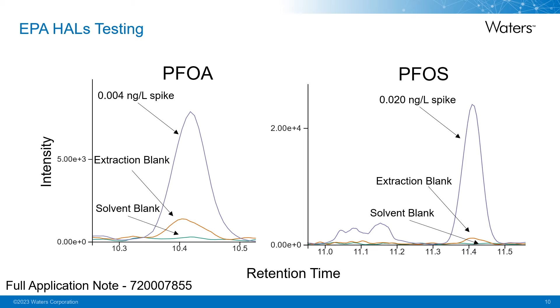So we can see that the solvent blank is completely blank for both PFOA and PFOS, indicating that the system itself, the mass spectrometer and the liquid chromatograph system, are PFAS free, or our isolator column is at least doing the job that it needs to do to delay those compounds. We're seeing a little bit of contamination in our extraction blank, but this is below the 1/3 limit that the EPA requires. And then we see a nice response for our extracted PFAS samples.